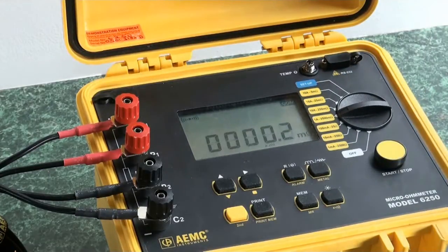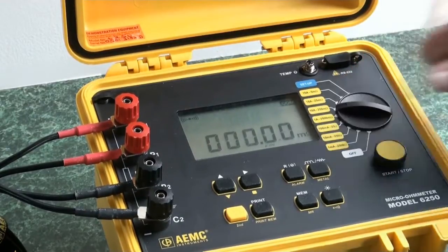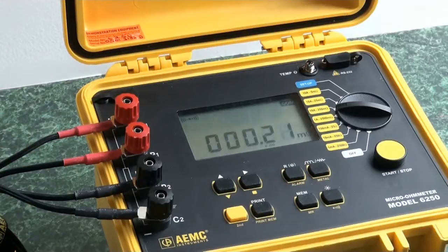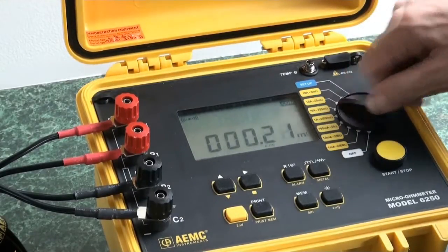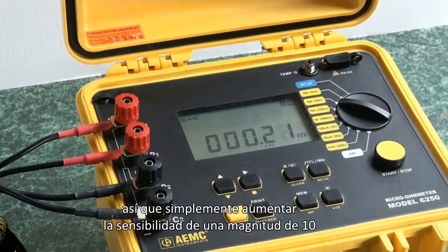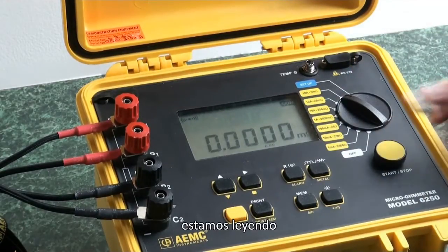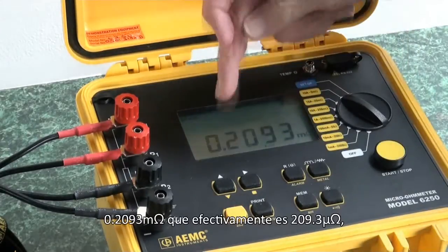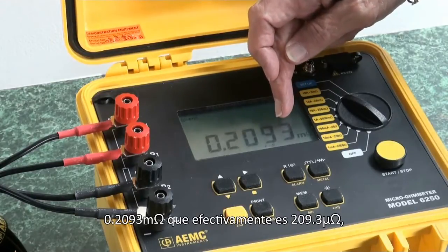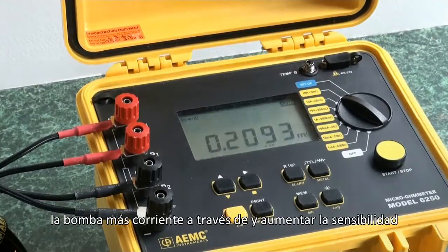We'll do a test. Now we're reading 0.2 milli-ohms. We'll crank it up some more — now we're going to run 10 amps through it. We shift decimal places and find it's actually 0.21. We can run it up to 10 amps on the 25 milli-ohm scale, increasing sensitivity by a magnitude of 10. Finally running 10 amps through it, we are reading 0.2093 milli-ohms, which effectively is 209.3 micro-ohms. So we see the sensitivity of this device as we increment up the scale, pump more current through, and increase sensitivity.